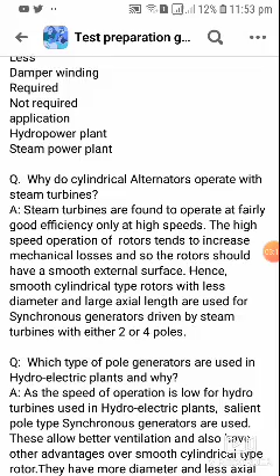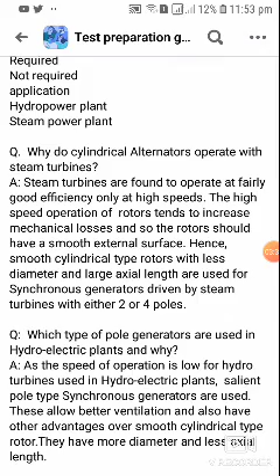Question number 9, why do cylindrical alternators operate with steam turbines? Answer: steam turbines are found to operate at fairly good efficiency only at high speeds. The high speed operation of rotors tends to increase mechanical losses, and so the rotors should have a smooth external surface. Hence, smooth cylindrical type rotors with less diameter and large axial length are used for synchronous generators driven by steam turbines with either 2 or 4 poles.